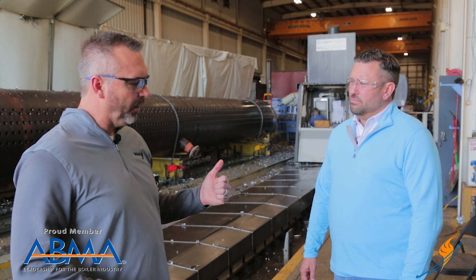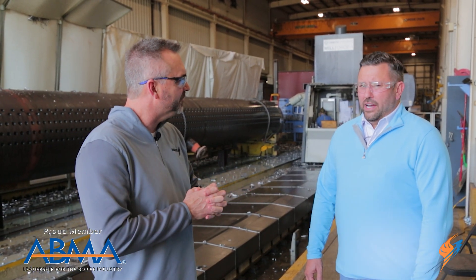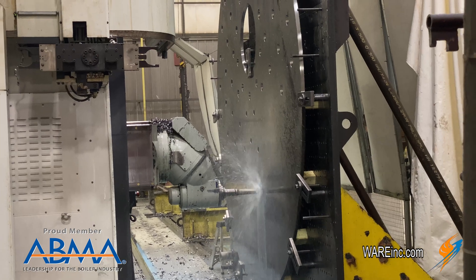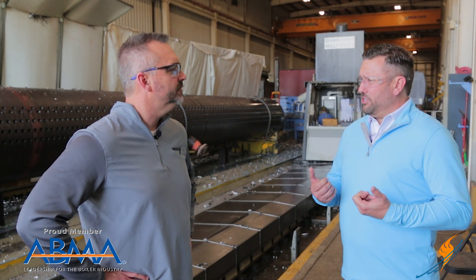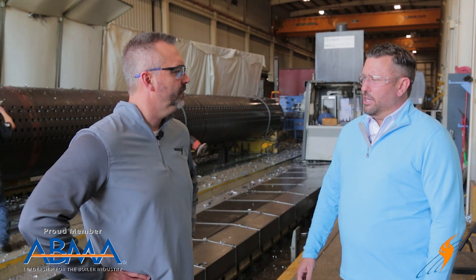We were talking with Oren a little bit about the ring that's inside the tube sheet — is that something you can do with this as well? Absolutely. This particular machine not only drills the hole, but it can do the ring groove within the same process. We use that ring groove — similar to what Oren had said — to ensure a secondary seat for that tube to the steam drum, and it just helps with the integrity of the joint.